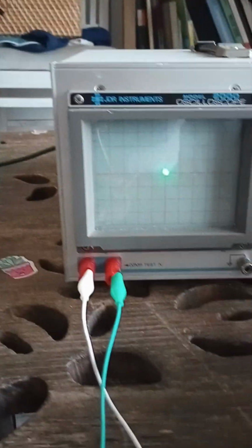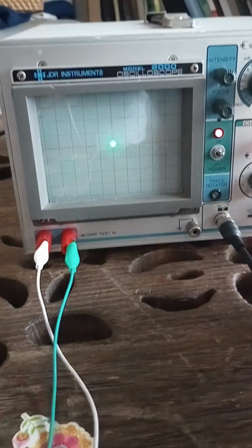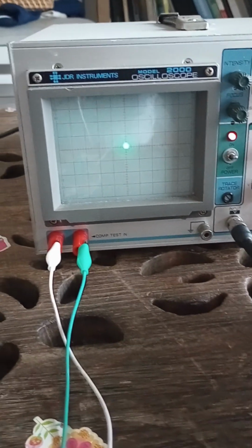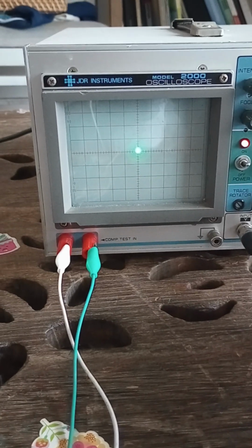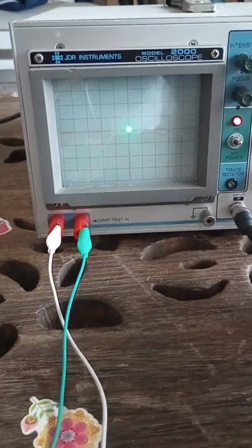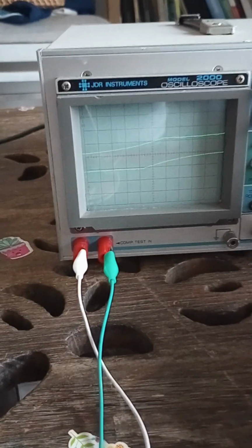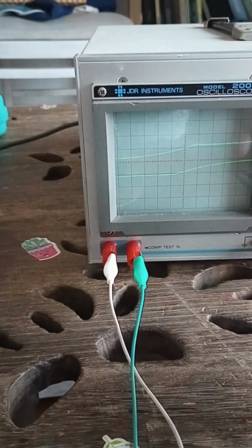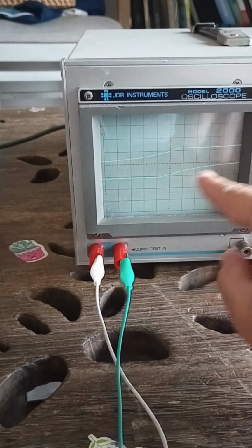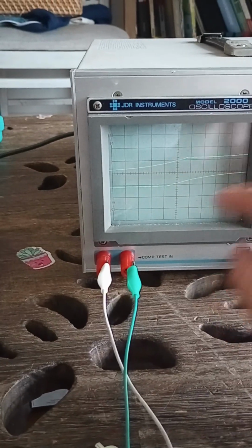And so what the component test will do is apply an 8 volt AC voltage that will be current limited to 2 milliamperes. Okay, and so let me press this component test. So now you have this curve here that we're going to need to adjust, and the x-axis is voltage and the y-axis is current.